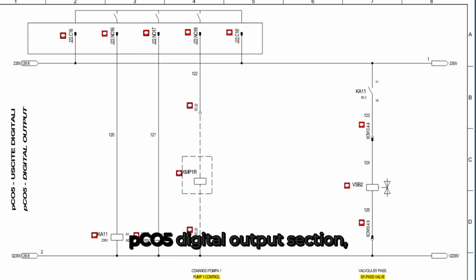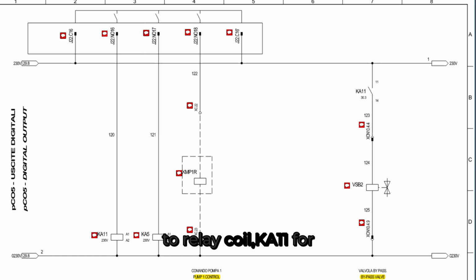This page continues the PCO5 digital output section, detailing how the PCO5 sends on-off signals to relay coil KA11 for solenoid bypass valve VSB2 at refrigerant circuit 2, and relay coil KA5 for the evaporator heat exchanger antifreeze heater, and the hot water side pump, an on-off command to the pump 230-volt relay coil. The pump command is a field-wired option and should be landed at terminals XC22, XC23. When VSB2's coil is energized, the valve opens, allowing bypass flow through the refrigerant circuit.